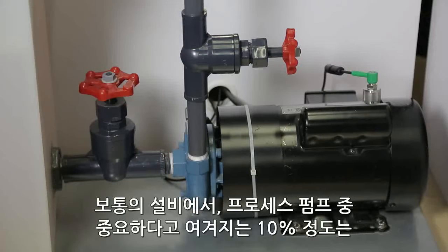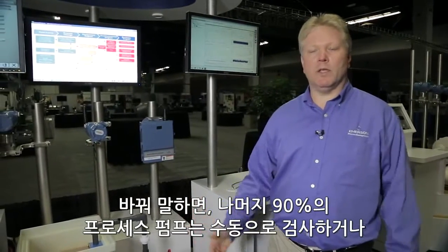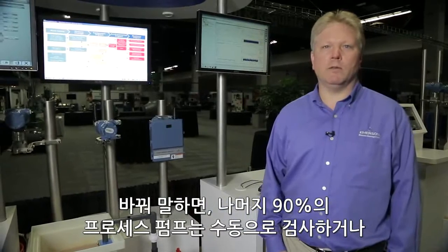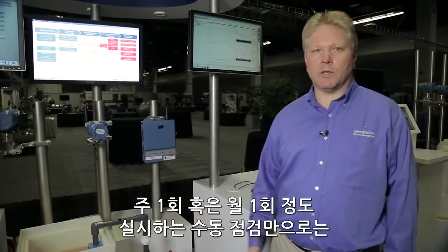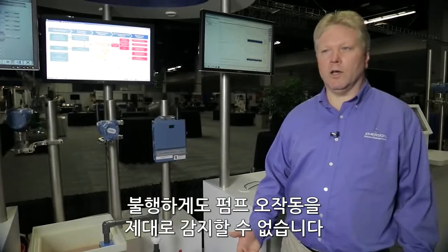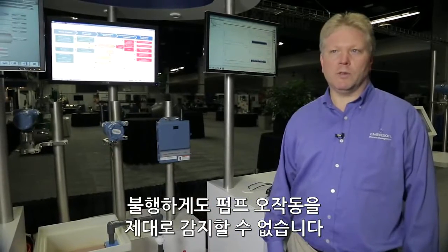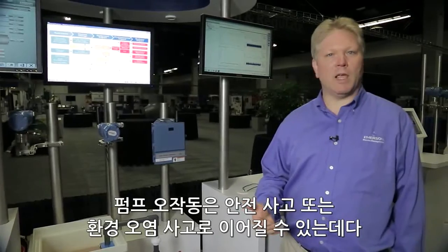Of process pumps in a normal facility, about 10% are deemed critical enough to actually have online monitoring. And what that means is that the remaining 90% of process pumps have to be checked either manually or through a preventive maintenance program. So these manual checks are once a week, maybe once a month, and unfortunately that's not quite good enough in order to catch all the pump failures. And any type of pump failure can lead to a safety or an environmental incident, plus the unfortunate, inevitable shutting down of your unit, which is a financial burden.